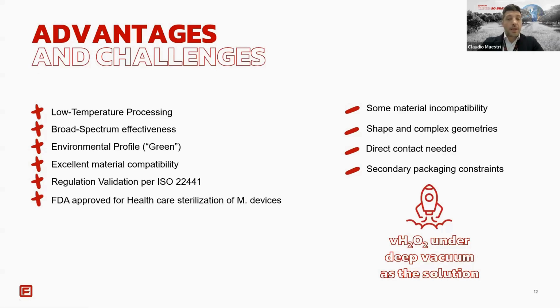Okay, here we are, back. H2O2 is considered a green sterilization modality because its active vapor breaks down into oxygen and water vapor. This eliminates the dangerous emissions associated with ethylene oxide. Excellent material compatibility. H2O2 has excellent compatibility with a wide range of metal and polymeric materials. It's suitable for several products, including general surgical instruments, endoscopes, implants with electronics, pharmaceutical containers, and pre-filled syringes. Regulation and validation as per ISO 22441 and FDA, as we already saw, approved for healthcare sterilization of medical devices.